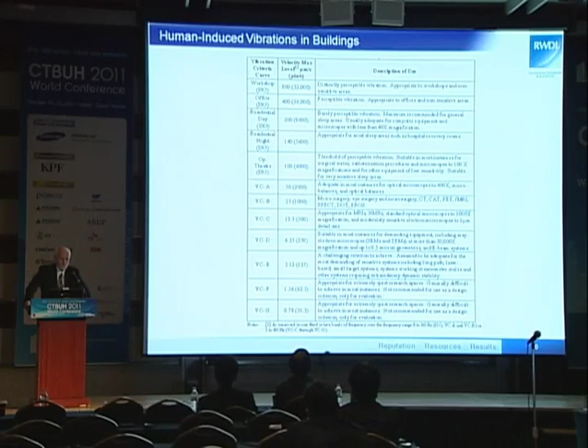Obviously it has to be better for that, and so on down. For an operating theatre, it's down to about 100 micrometers per second. This is really getting down to the threshold of perception, and it's suitable in most instances. For some magnifications, on the order of 100 times, it's also adequate. But if you're doing eye surgery, you've got to be about 4 times more stringent than that.